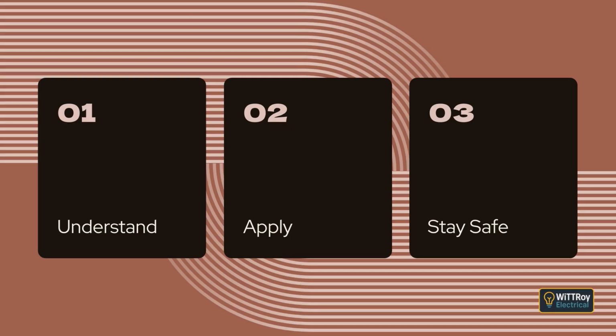Before any installation is put into service, whether it is new, extended, altered, or repaired, it must be inspected and tested. This is not optional. The purpose is to confirm that the work complies with the standard. Inspection and testing must be carried out as far as practicable, meaning as thoroughly as site conditions allow. During this process, precautions must be taken to avoid danger to people and damage to equipment or property.